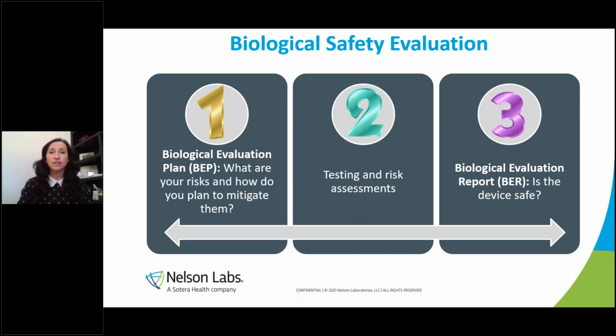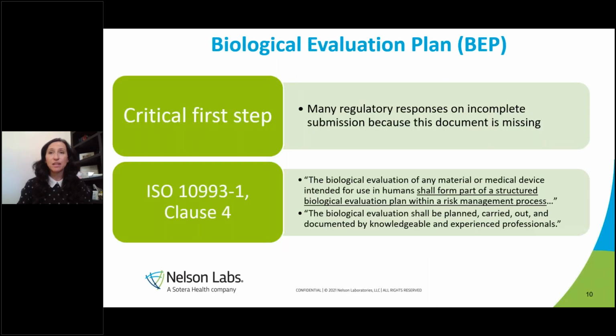Okay, back to this slide where we break it up into the three parts. We're going to dive into a biological evaluation plan and talk about some details there first. So this BEP is really a critical first step in biocompatibility. I do see a lot of responses from submissions that say, there's no risk assessment that says why you did the testing you did, why this is supposed to support the safety of the device. So agencies really do expect proper documentation, and a biological evaluation plan is not only great for your submission, but it's great for a company.